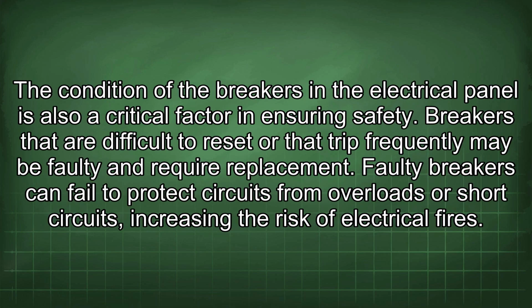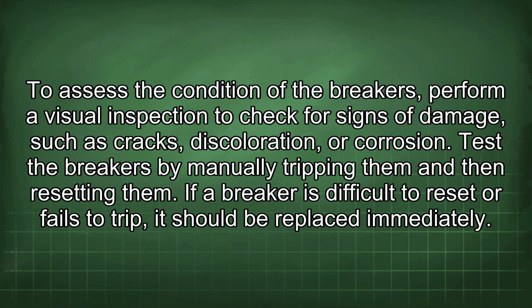The condition of the breakers in the electrical panel is also a critical factor in ensuring safety. Breakers that are difficult to reset or that trip frequently may be faulty and require replacement. Faulty breakers can fail to protect circuits from overloads or short circuits, increasing the risk of electrical fires. To assess the condition of the breakers, perform a visual inspection to check for signs of damage, such as cracks, discoloration, or corrosion. Test the breakers by manually tripping them and then resetting them. If a breaker is difficult to reset or fails to trip, it should be replaced immediately.